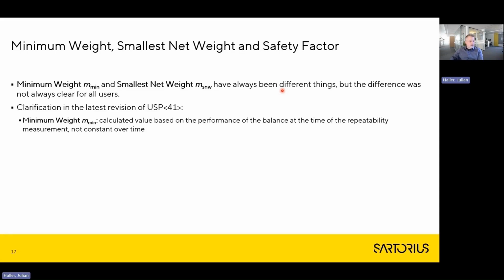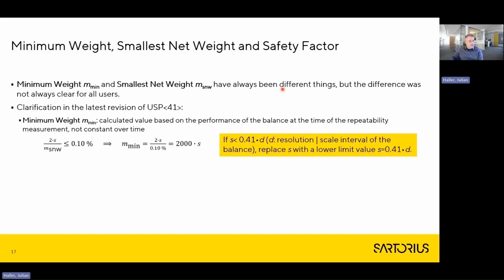The minimum weight is defined as the calculated value based on the performance of the balance at the time of the repeatability measurement, which means it is not constant over time. It can be derived from the acceptance criterion for the repeatability performance check. If you take that equation on the left side and reshape it, it yields that 2 times the standard deviation divided by 0.10%, or 2000 times the standard deviation, is the smallest weight that still satisfies the acceptance criterion. Again, of course, if the standard deviation is smaller than 0.41 digits, it should be replaced with that value. The smallest net weight, in contrast, is a user-defined requirement which usually does not change over time.